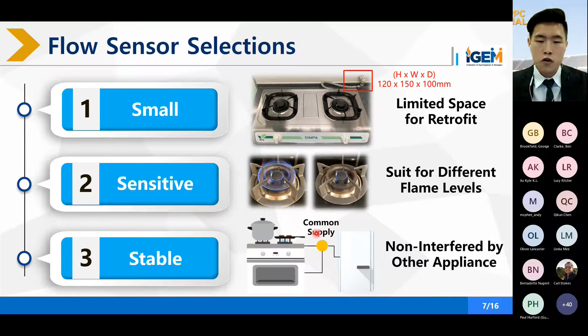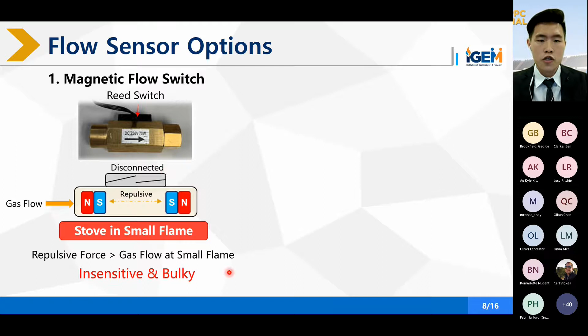The first one is the magnetic flow switch, which has a reed switch on top. But through the experiment, I found that when the gas flows under the small flame condition, the force is not strong enough to overcome the repulsive force between the magnets. So the reed switch cannot be connected and cannot give us an output signal. Therefore, the magnetic flow switch is considered to be insensitive under the small flame, and it is also bulky in size.